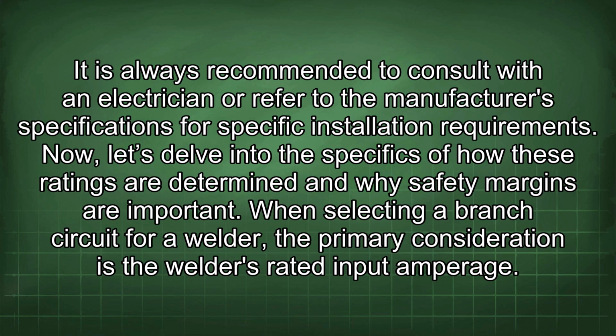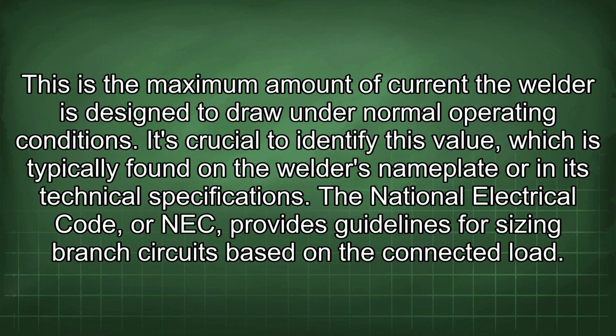When selecting a branch circuit for a welder, the primary consideration is the welder's rated input amperage. This is the maximum amount of current the welder is designed to draw under normal operating conditions. It's crucial to identify this value, which is typically found on the welder's nameplate or in its technical specifications. The National Electrical Code, or NEC, provides guidelines for sizing branch circuits based on the connected load.